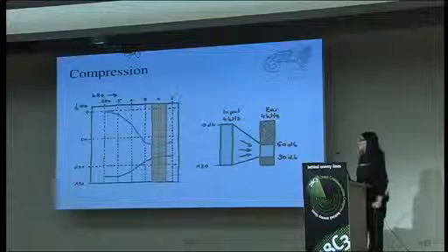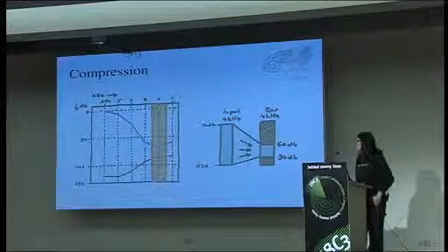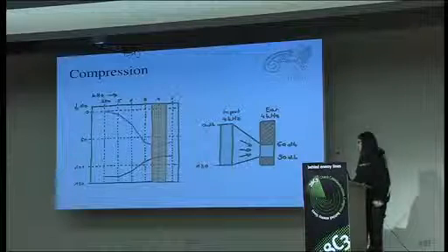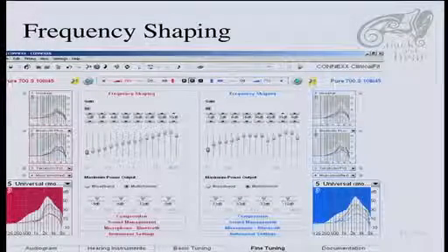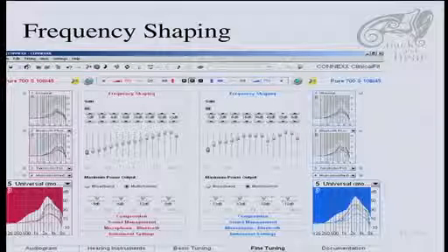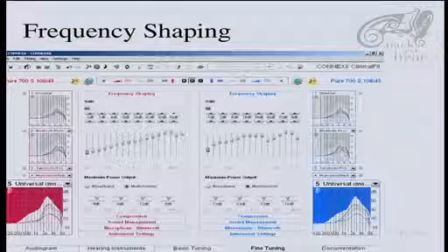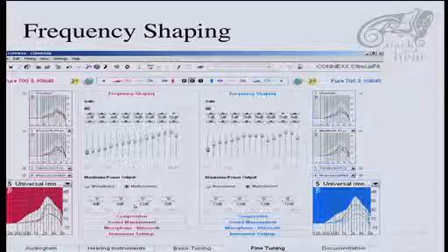And this is called compression. This should not be mistaken for compression in audio files like MP3 or something. It's a little bit different. And if you have a look at the software that is used to adjust hearing aids, it looks like that, with the mouse here. This controls the amplification, and this here reduces the maximum level. So my hearing aids can at maximum do 108 decibels, and if you have -12, you just subtract it from that.